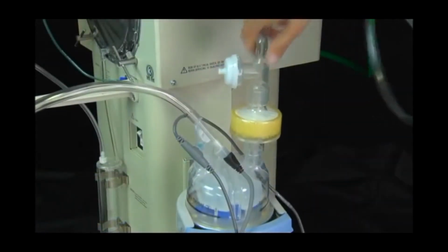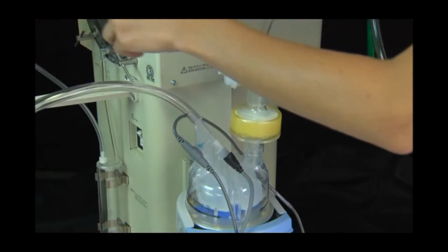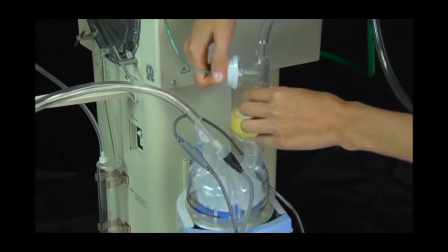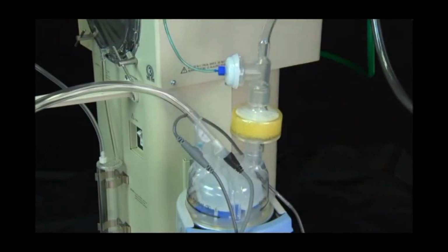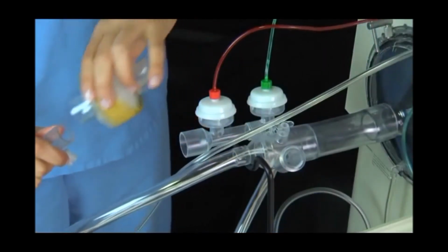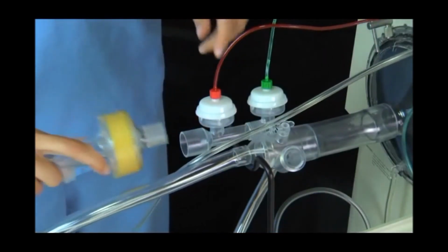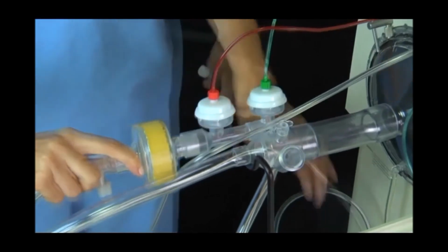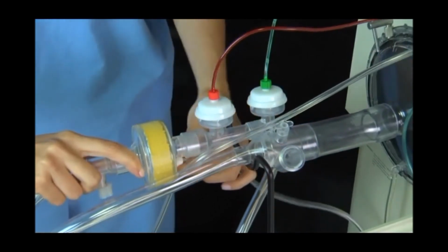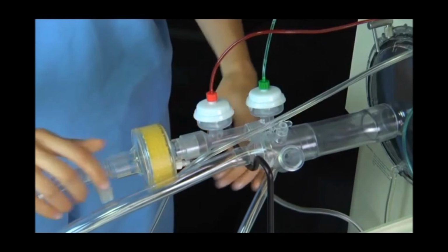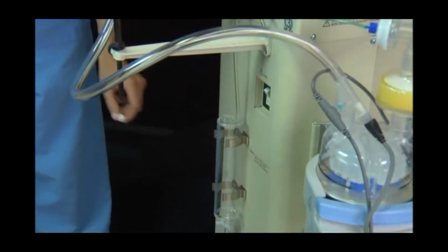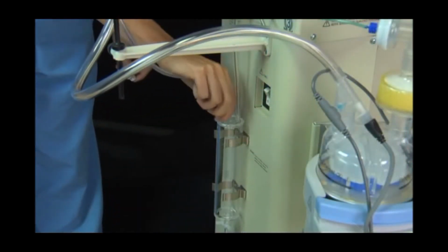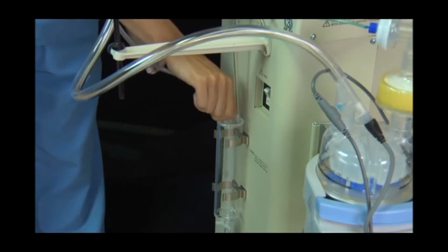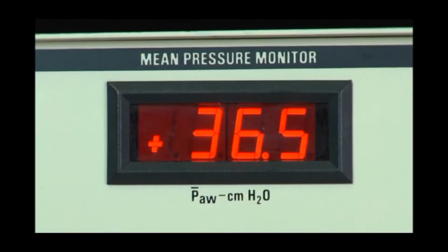Place the inspiratory filter on the fitting next to the control valve and connect to the inlet of the humidifier chamber. Place the expiratory filter in the circuit. Position the luer fitting at the bottom and facing the 3100. Connect the drain tubing from the bottom of the filter to the luer fitting on the top of the water trap. As the dry filter becomes wet, you may notice a slight increase in mean airway pressure or amplitude.